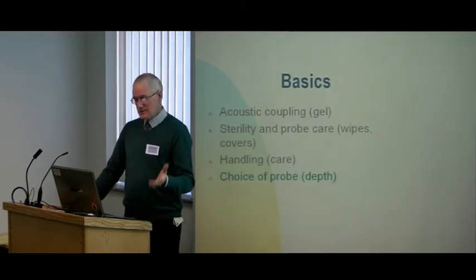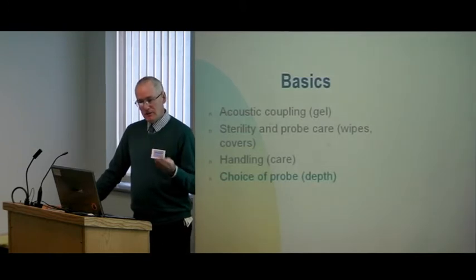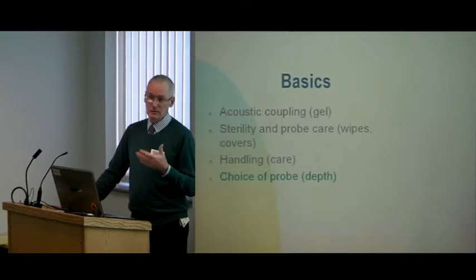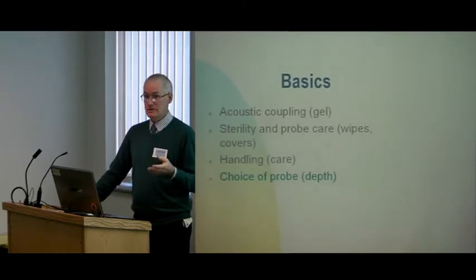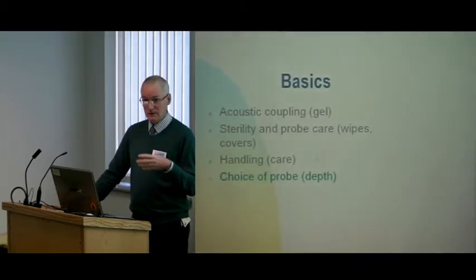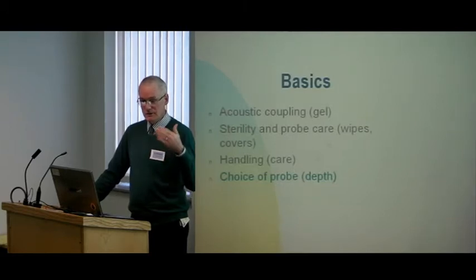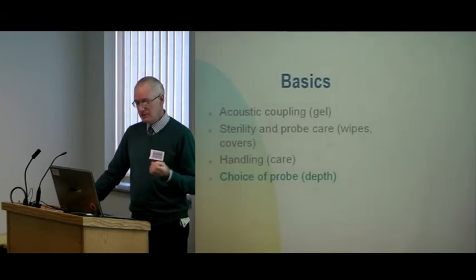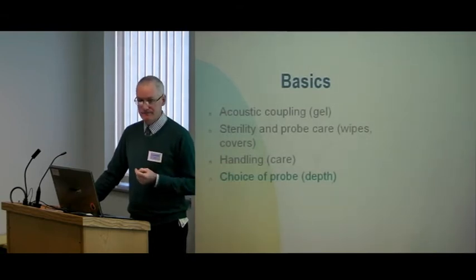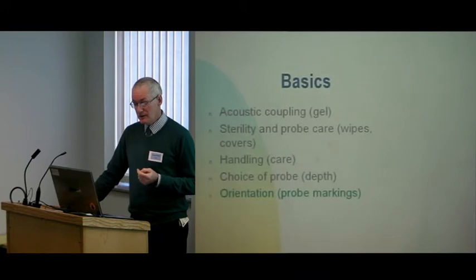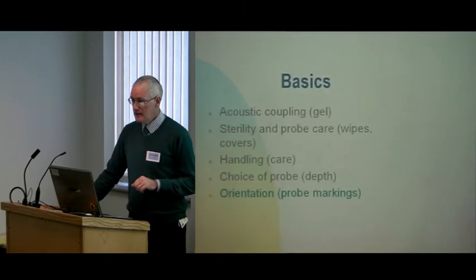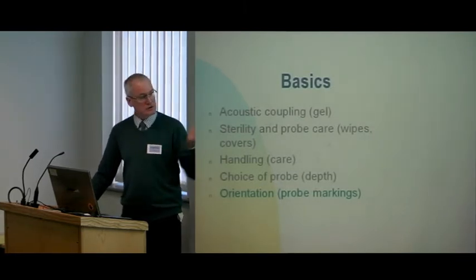When you're buying machines, make sure you buy a probe that's capable of superficial imaging and a probe which is capable of deep imaging. You may find that there is a probe which offers both superficial and deep. I doubt whether it'll be successful in both those practices, but you must always bear in mind, you must be visualizing superficial and you must be visualizing deep. Superficial structures require a higher frequency, and deeper structures require a very much lower frequency in order to penetrate through the soft tissues.